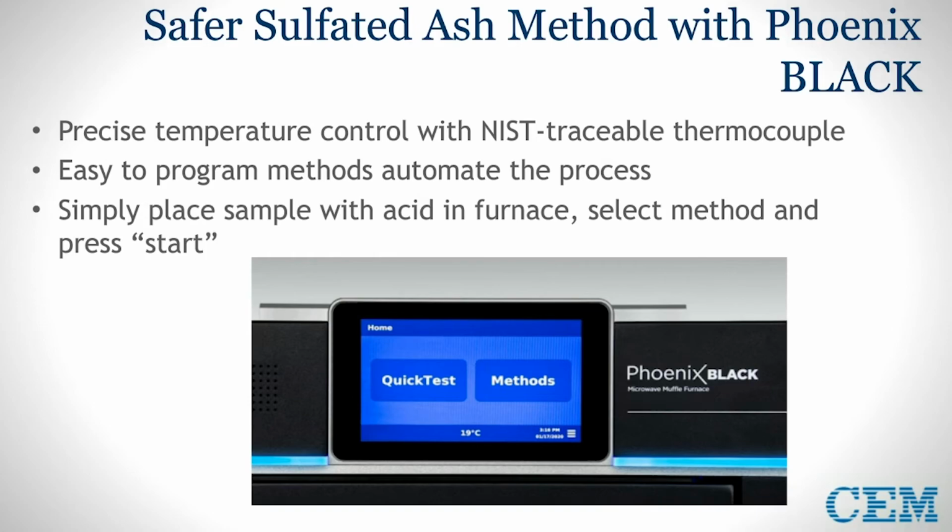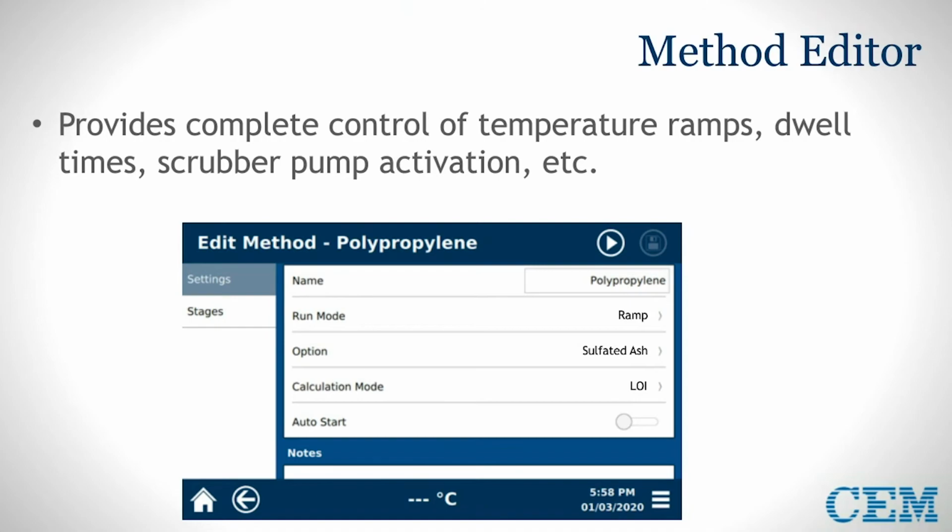Here's a quick look at what the method editor looks like for Phoenix Black. It's very simple and straightforward. It provides complete control of temperature ramps as well as dwell times, scrubber pump activation, and any other parameters that you want to control throughout that sulfated ash test.